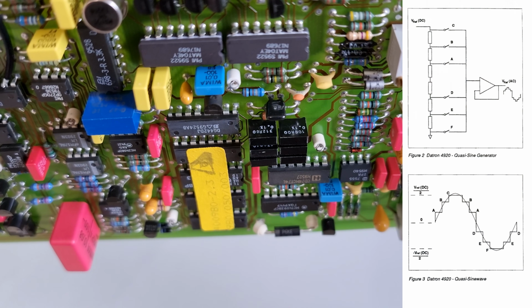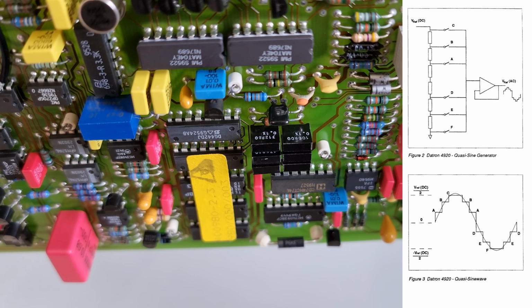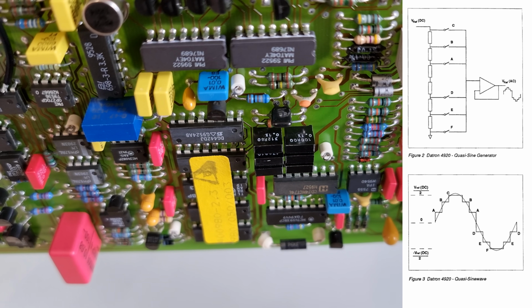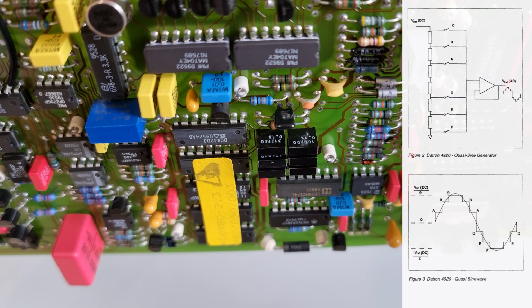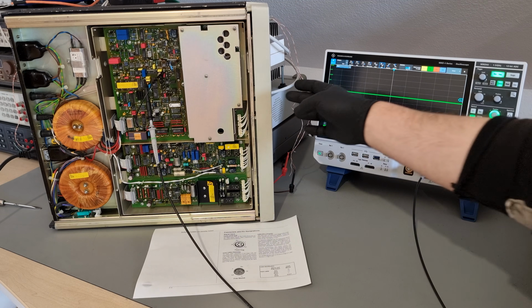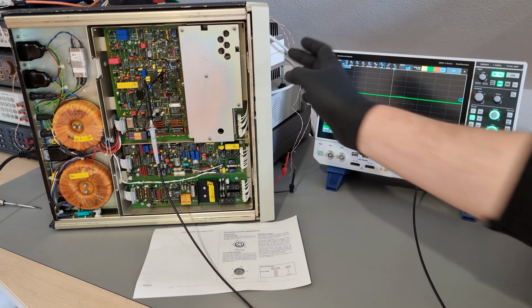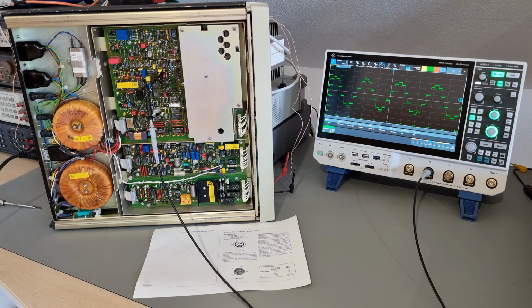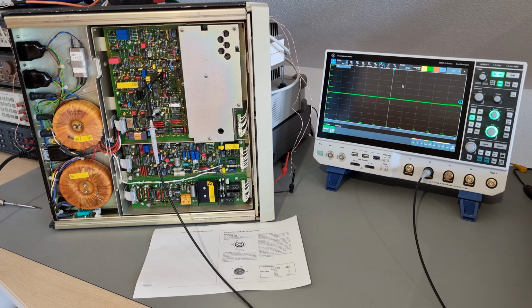The low-resolution but super stable quasi-sine monstrosity generated here is apparently invoked in every single measurement cycle to check and digitally correct for the RMS detector gain, just before it's let loose on an actual signal of interest. Oh, that is so cute.